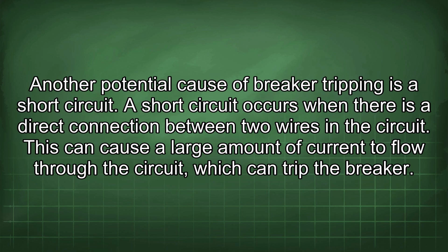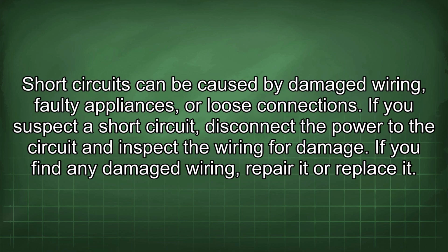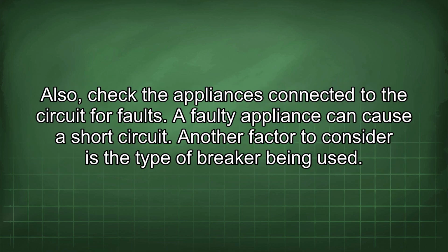Another potential cause of breaker tripping is a short circuit. A short circuit occurs when there is a direct connection between two wires in the circuit. This can cause a large amount of current to flow through the circuit, which can trip the breaker. Short circuits can be caused by damaged wiring, faulty appliances, or loose connections. If you suspect a short circuit, disconnect the power to the circuit and inspect the wiring for damage. If you find any damaged wiring, repair it or replace it. Also, check the appliances connected to the circuit for faults. A faulty appliance can cause a short circuit.